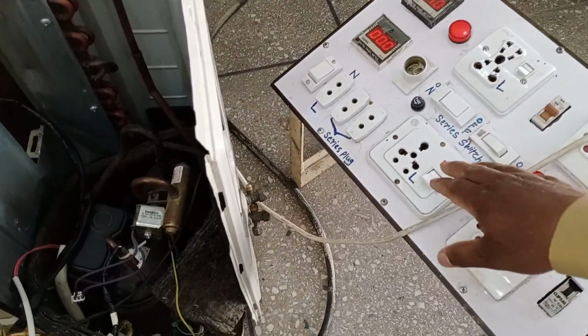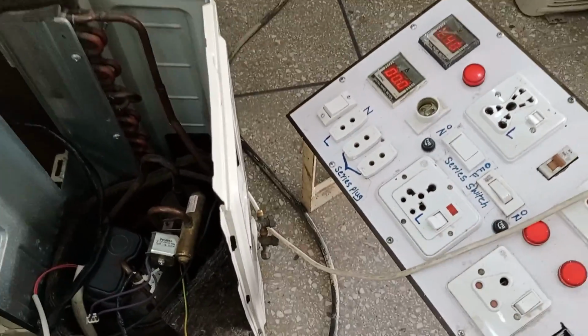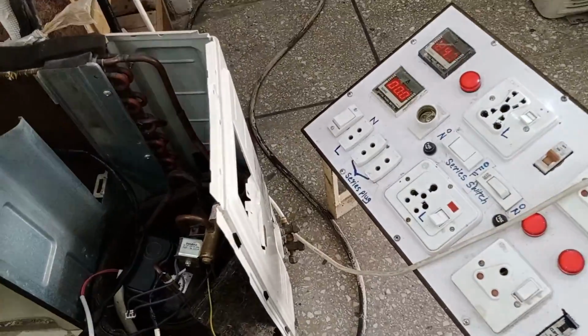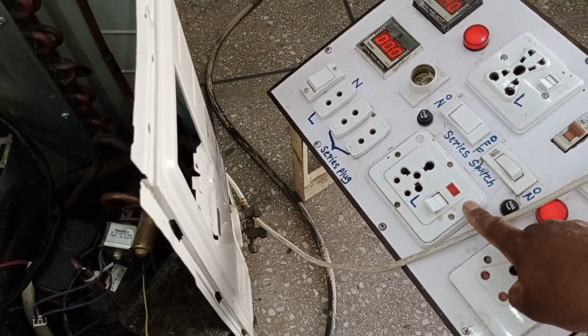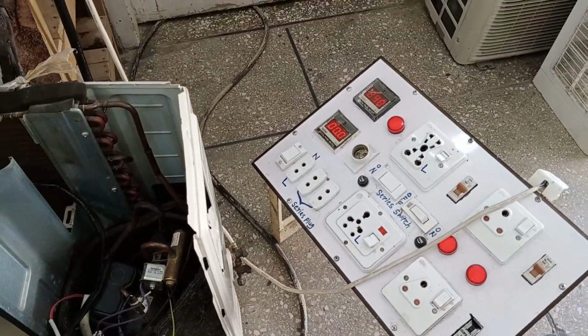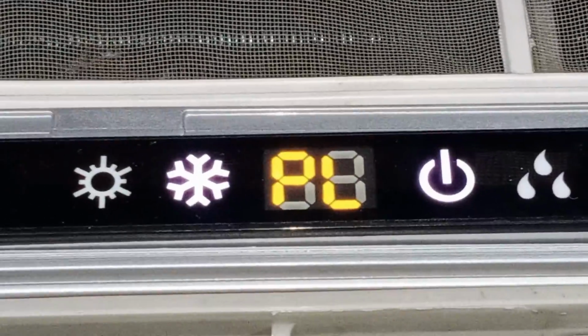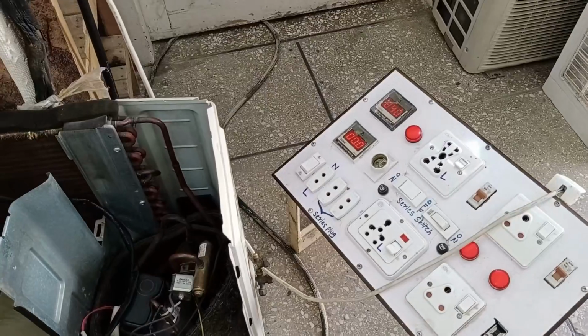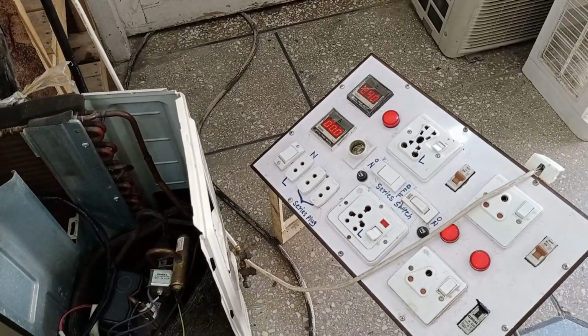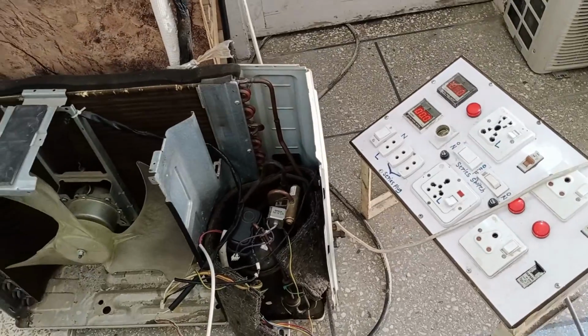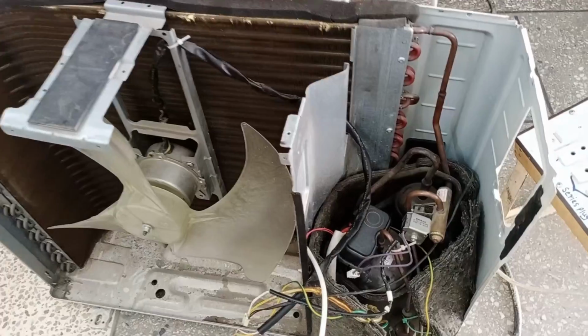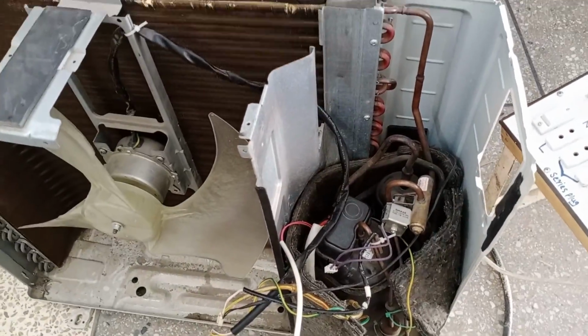So, if you just plug the electrical plug into your power socket to start the unit, and the PL is displayed, this means that the voltages passing into your power socket are lower than the rated voltages of the unit, then the PL error code will start to show on your air conditioner. Then, you will need to fix the voltages on your power outlet. The next situation could be that you started the unit. Then, you have to check what it is doing on the outdoor unit.